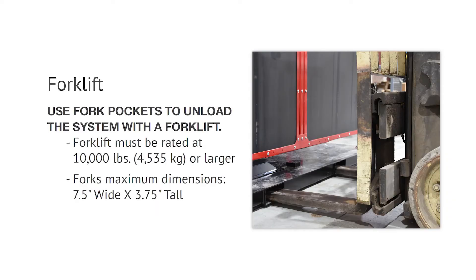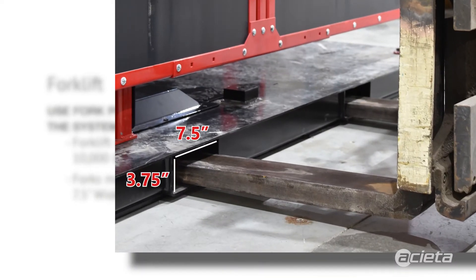The method for unloading your Acieta FastArc TT: your forklift must be rated at 10,000 pounds or larger, and your forks' maximum dimensions must be seven and a half inches wide by three and three-quarter inches tall.